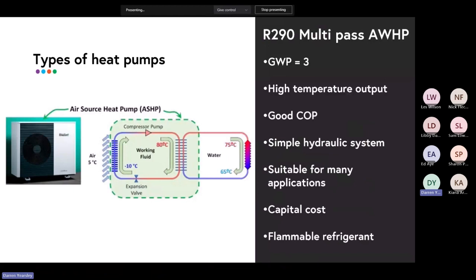The hydraulics are very simple. It's much more consistent to how you would design a mechanical boiler system, where you've got flow and return, and on the potable side, your cylinders are plumbed up in parallel. It's also suitable for many applications. So it's not just hot water applications. What you can do, any sort of space heating application, whether it's radiant systems, fan coils, anything like that, because it's very comfortable operating on a 5 or 10 degree difference, then you can use them multi-use in all sorts of applications.